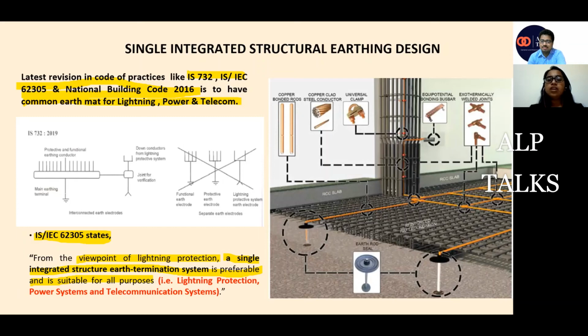If I have installed the pits only for the lightning protection system, like I have taken 10 down conductors from the roof, given 10 earth pits dedicatedly to those down conductors, and interconnected them, then I cannot combine it with my electrical equipment, because that earthing was dedicated to the lightning protection system for less than 10 ohms. But for applications where I am making a common grid, a complete earthing grid, I can combine lightning earthing with power and telecom.